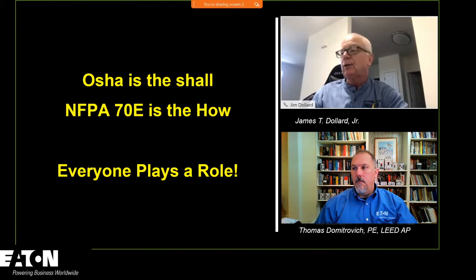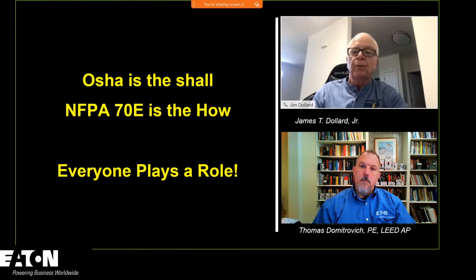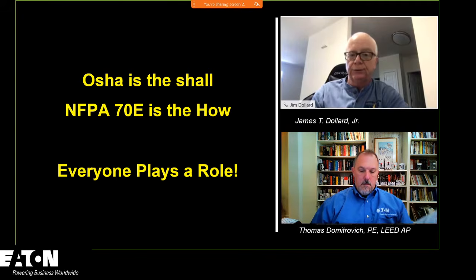So getting back to who is going to enforce arc flash labeling, when you get into 130.5H, the very last paragraph says the owner is responsible for the label. So if the owner chooses to install NFPA 70E type labels, they can. If they choose not to, they don't have to, because it's not a requirement in federal regulation. There's no federal regulation backing that up.